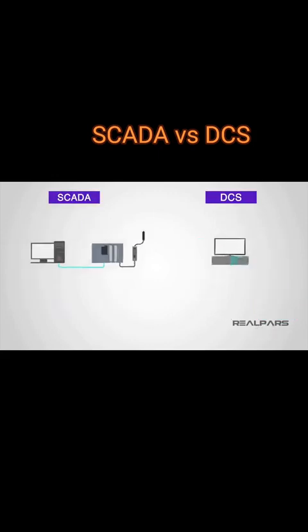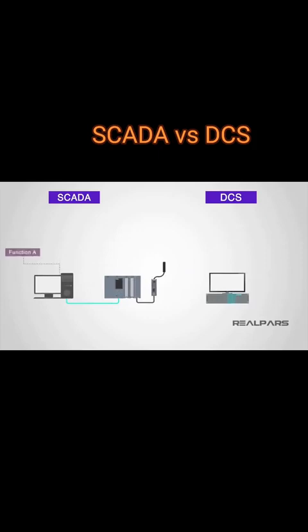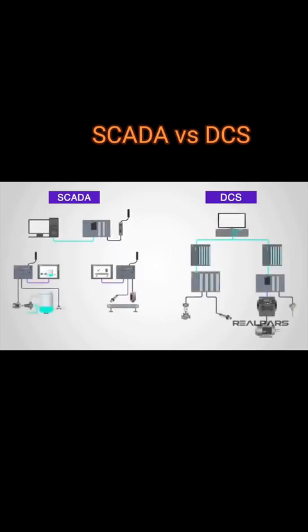While this was, at least in the earlier days, more cumbersome in the SCADA implementation, the DCS had many predefined functions that could be customized and deployed for various applications. This didn't eliminate the need to write code. However, it did help to facilitate faster integration because less time would be spent writing code for commonly used functions. Processing times are somewhat slower in the DCS versus the PLC RTU SCADA environment. While this is not necessarily problematic, it could have an impact on processes that are very time-sensitive.